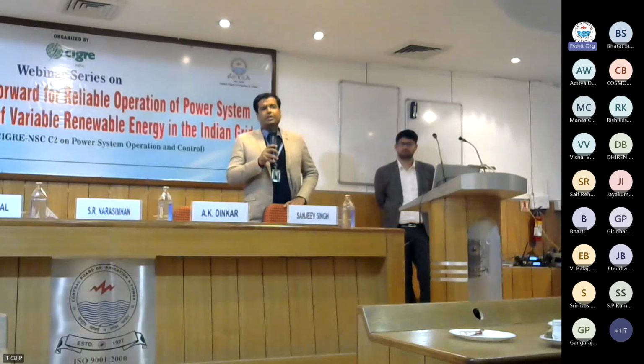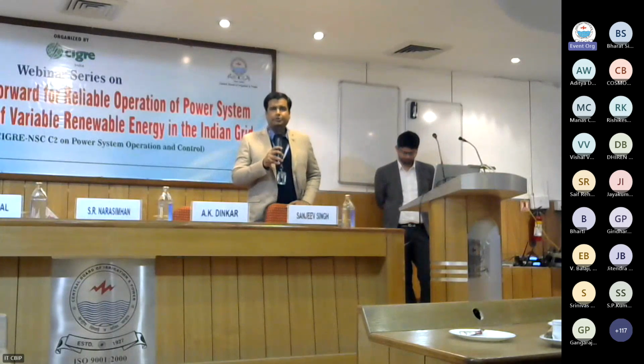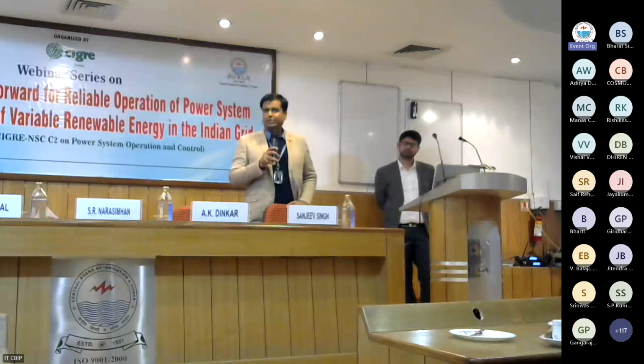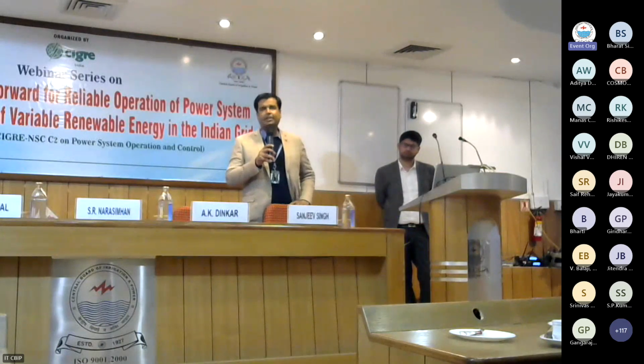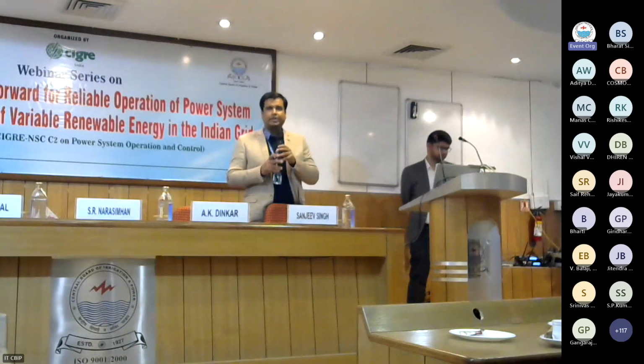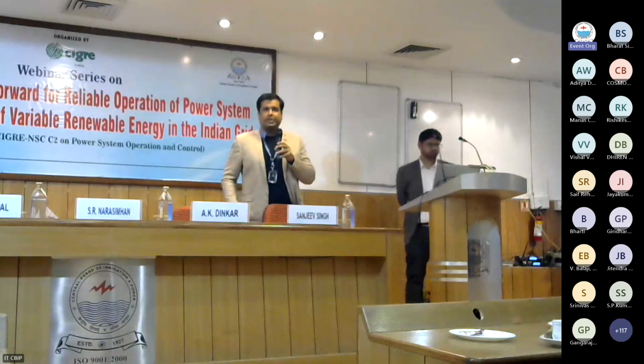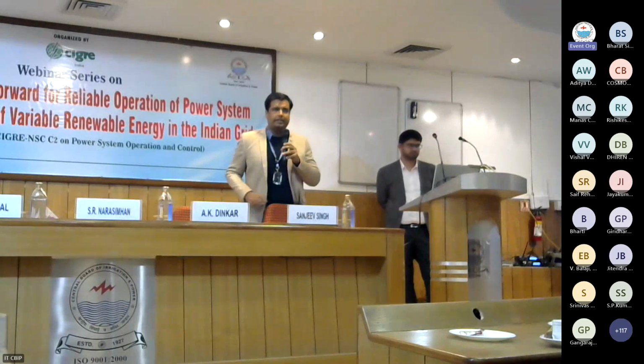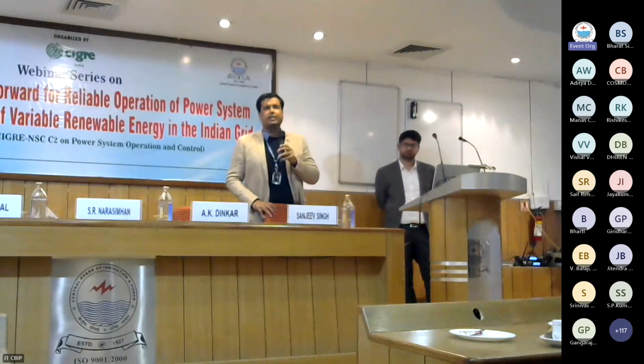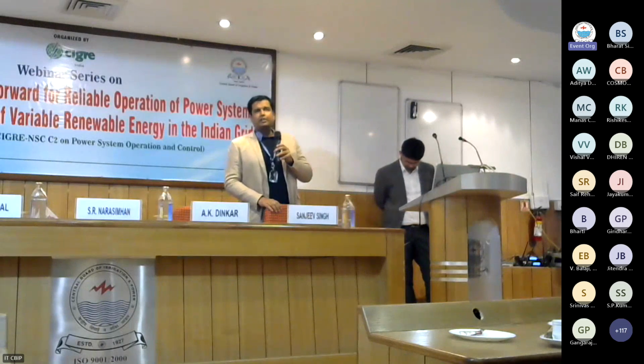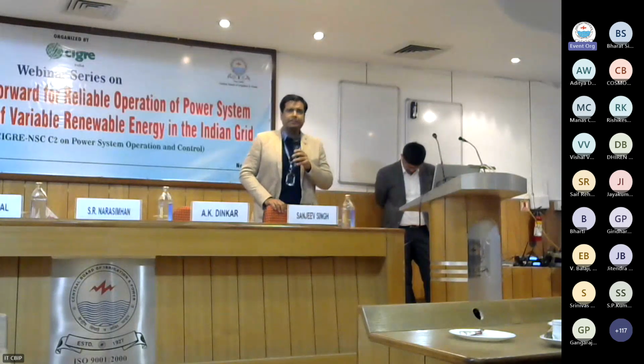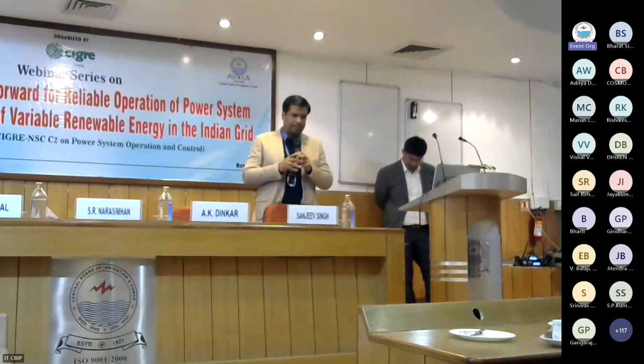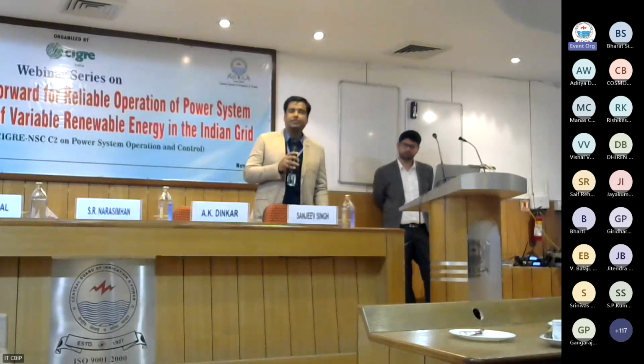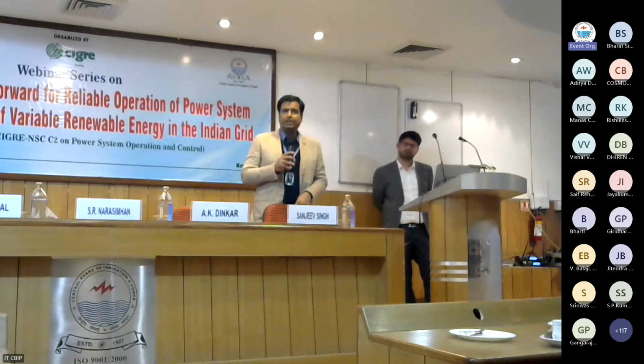So, however, in the CS standards, we expect very soon to have detailed requirements for all these devices, including the inverter duty transformer, because that has been identified in our report also as an important equipment for the RE plant. So we expect the IDT standards very soon. Second part regarding the harmonics, in the Indian power system, and as per the CEA requirements, harmonic computation as well as harmonic checking is there. So yearly, and that time duration is also mentioned.